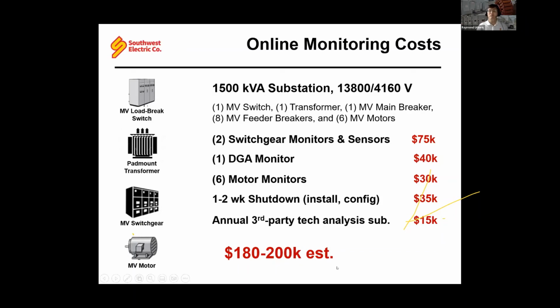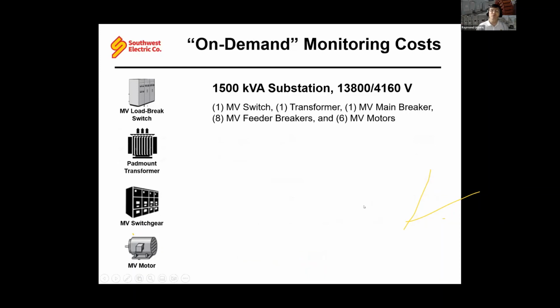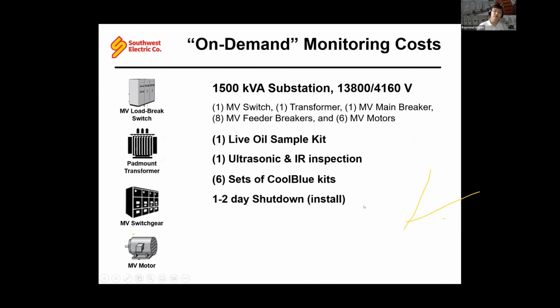We were starting out around 180 to 200,000 in order to properly install online monitoring for this given substation. If you use the examples and suggestions we mentioned, it's not a one-for-one. You're not getting continual monitoring. You're doing it on demand when you want it, but it's for a lot more manageable cost for your budget, and you still get a lot of that benefit that you wouldn't normally have.